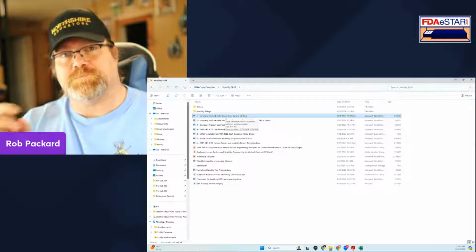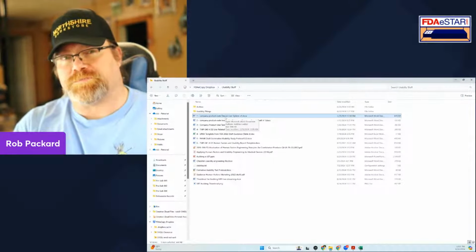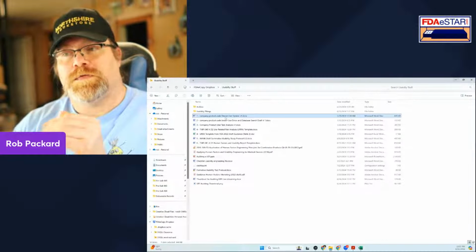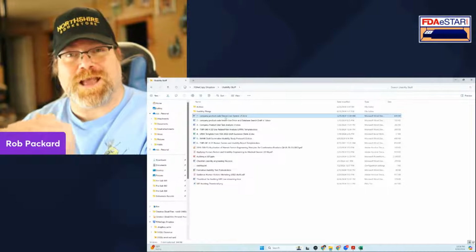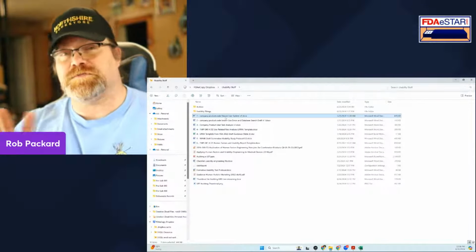So does it have a knob? Does it have a switch? Does it have a touch screen? Those are the things that they want in the use specification. So all those are the documents the FDA wants. Well, they don't have it really spelled out in a guidance document: this is what you should submit. They haven't incorporated that into the eSTAR yet.